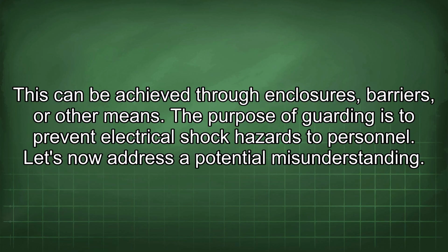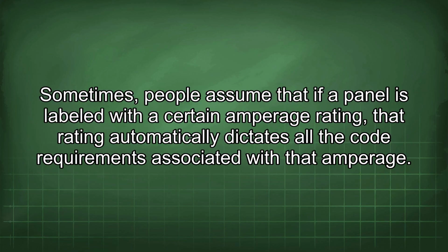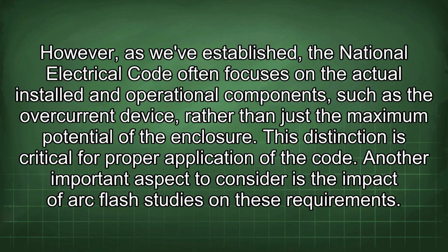Let's now address a potential misunderstanding. Sometimes people assume that if a panel is labeled with a certain amperage rating, that rating automatically dictates all the code requirements associated with that amperage. However, as we've established, the National Electrical Code often focuses on the actual installed and operational components, such as the overcurrent device, rather than just the maximum potential of the enclosure. This distinction is critical for proper application of the code.